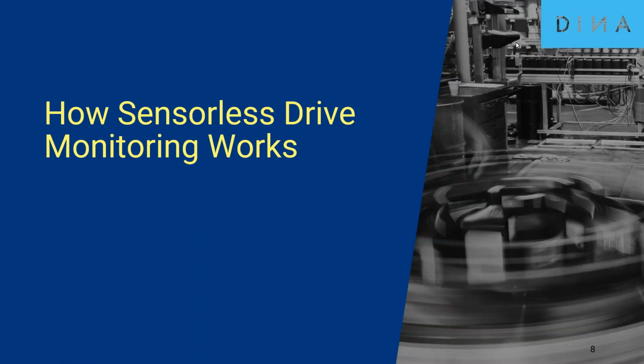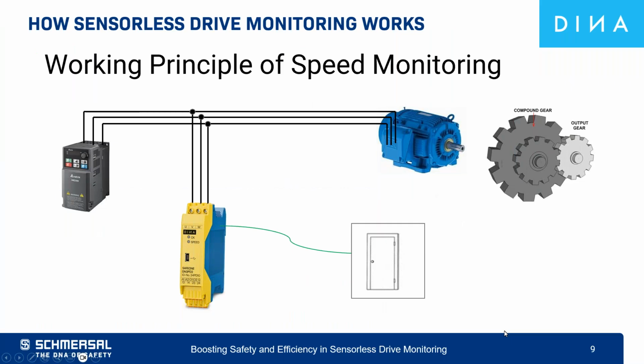Yes, the DINA SafeOne sensorless modules are designed for easy installation and connection. The primary difference between sensor-based systems and sensorless modules is the installation method and complexity. Traditional sensor-based systems require mounting, wiring, and commissioning additional hardware, sensors on the motor or axis itself. Sensorless monitoring modules eliminate this complexity by getting all necessary diagnostic data directly from the drive's electrical lines.